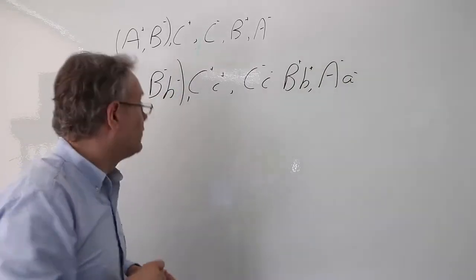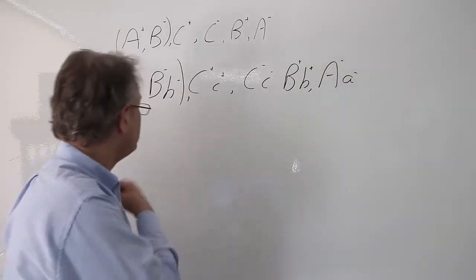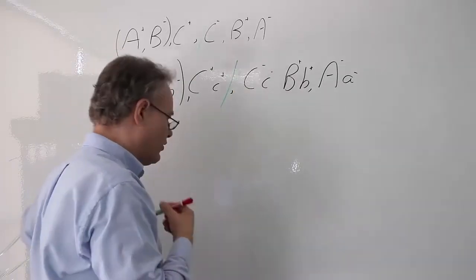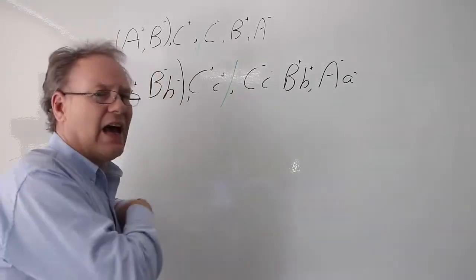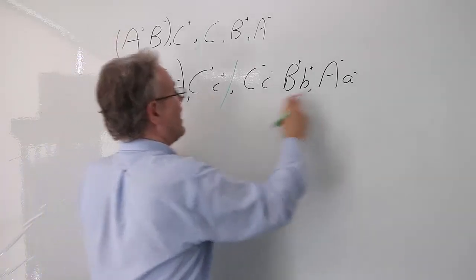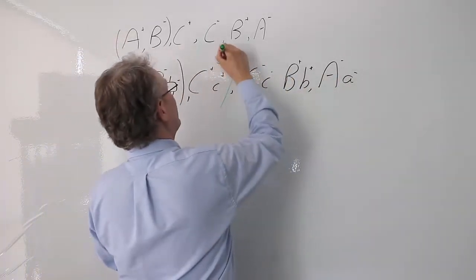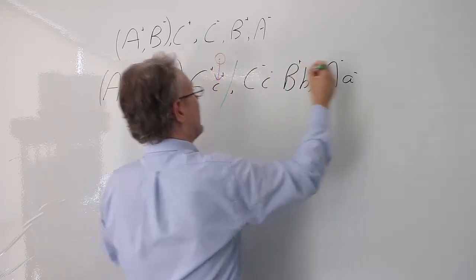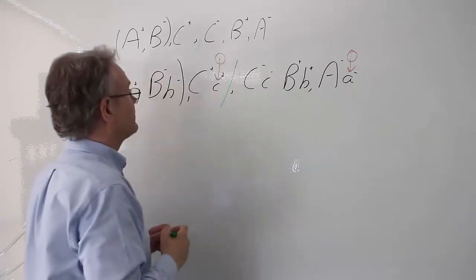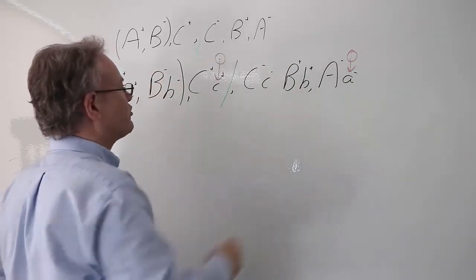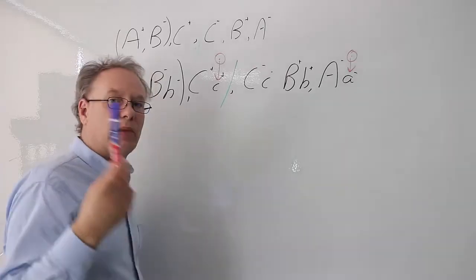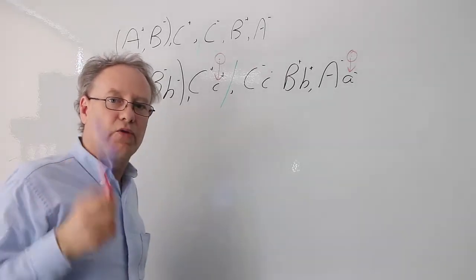So now I'll put my divider in there, and then I'm going to define my group selectors. Now, we know the group selector is the last action in every group. In this case, it's easy. It's this guy and that guy. Easy. So they are the guys that get air. The group selectors get air directly from supply. Now, everything else in this group is going to get supplied directly from the relay valves.